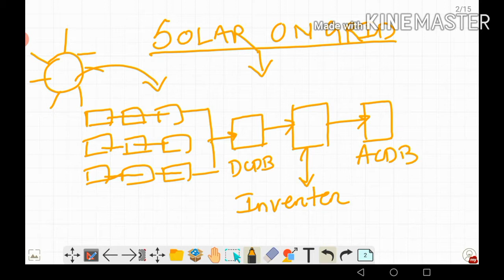Then the inverter will convert the energy to AC, and before connecting to the load, we will have to connect the ACDB to the system. The ACDB is the AC distribution box, and this is also a protection device which gives protection between the loads and the PV plant. If ever any fault occurs at the load or at the PV plant, it will isolate the load from the PV plant. So the ACDB is simply a protection device.